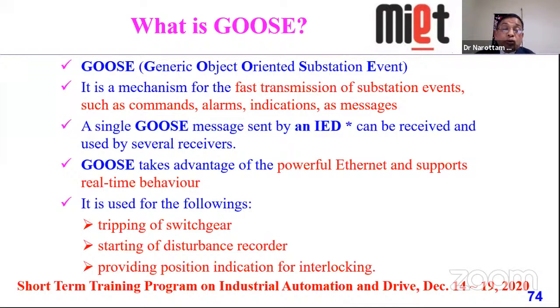GOOSE takes advantage of powerful Ethernet and supports real-time behavior, so you get the message instantly. This is also useful for tripping of switchgear, starting of disturbance recorders, providing position information, and indication of interlocking if there is any issue that needs to be found out.